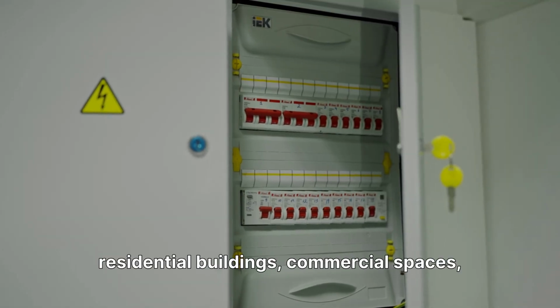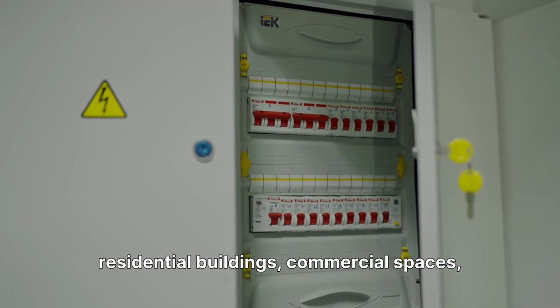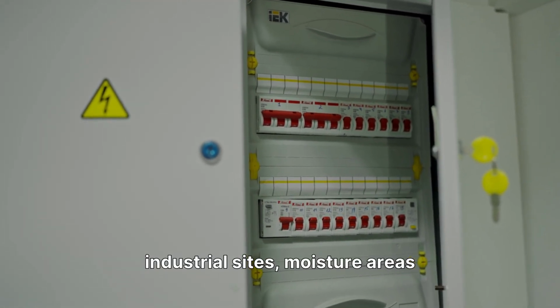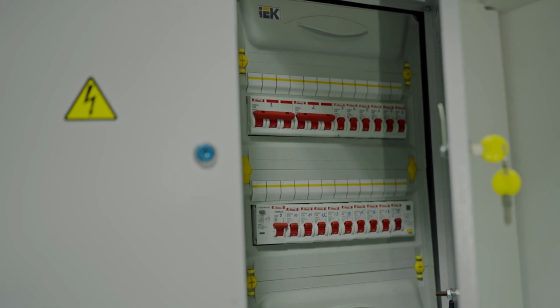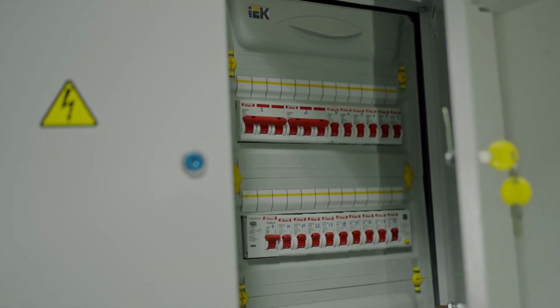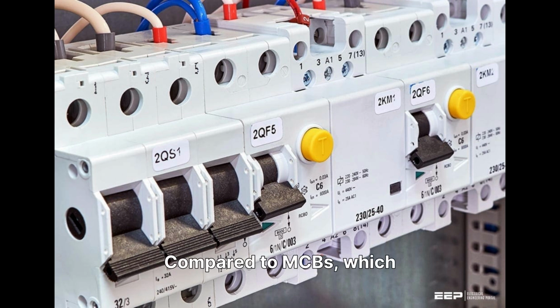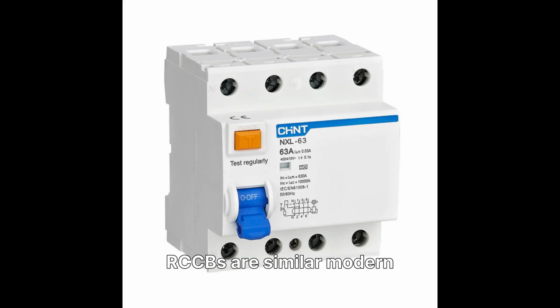ELCBs are installed in residential buildings, commercial spaces, industrial sites, moisture areas like bathrooms and kitchens, outdoor circuits, and vulnerable equipment zones. Compared to MCBs, which handle overcurrents and shorts, ELCBs focus on earth leakage for shock prevention. RCCBs are similar modern equivalents, while RCBOs combine leakage and overload protection in one unit.